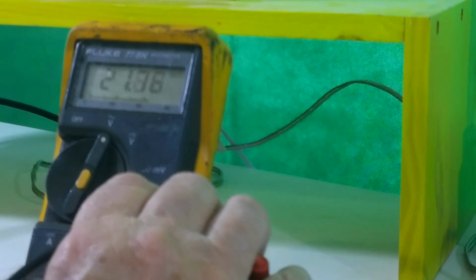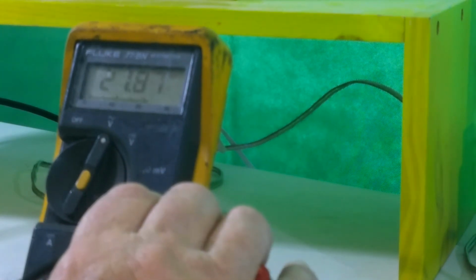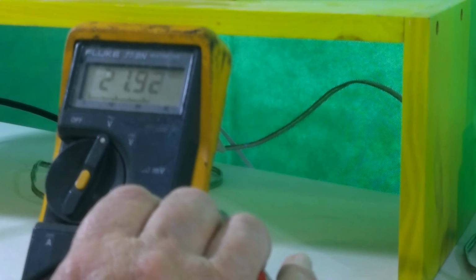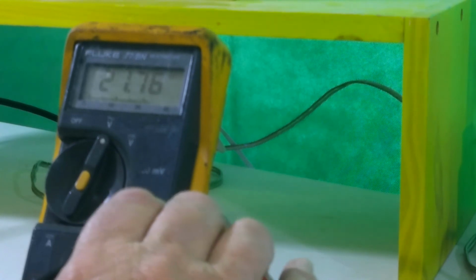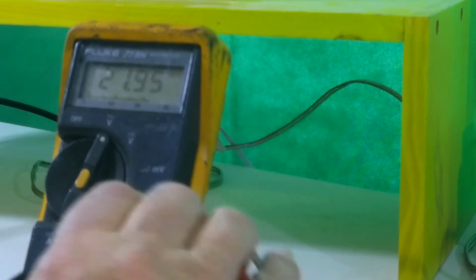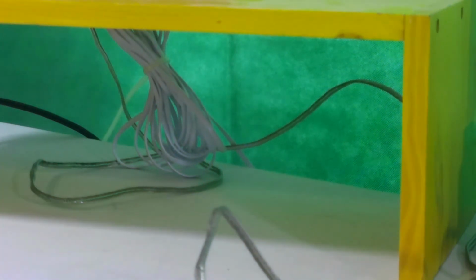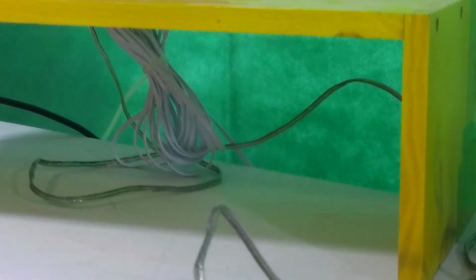Remembering that when this communicates, it will drop as low as 18.5, 19 volts. Okay, now I'm going to remove this. Now, if that voltage is not there, check the wiring between the MIM and the field unit, tracing the wire and then finding the faults in it.